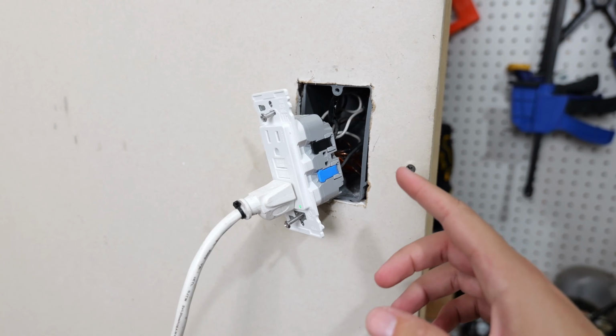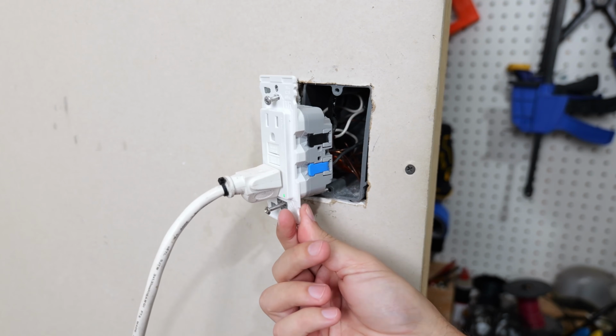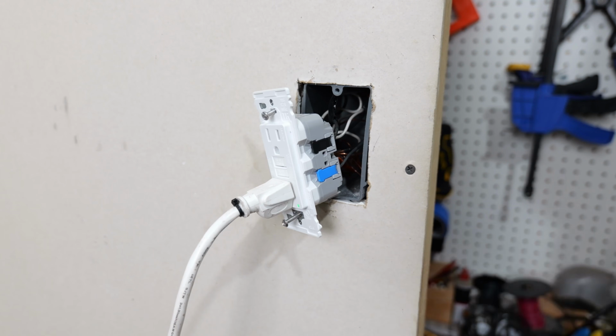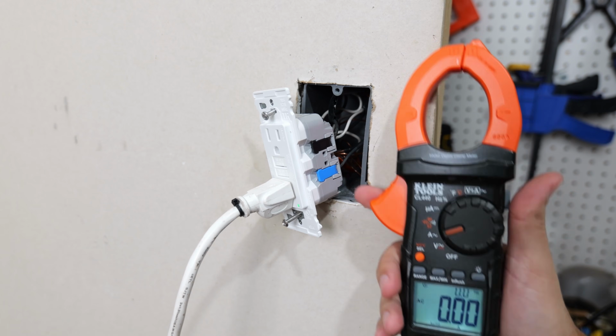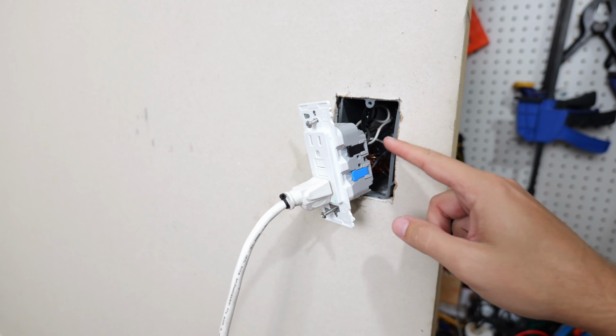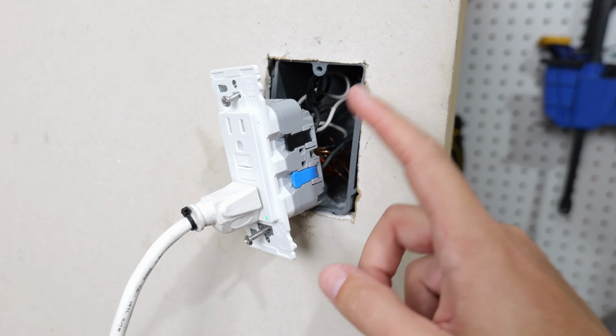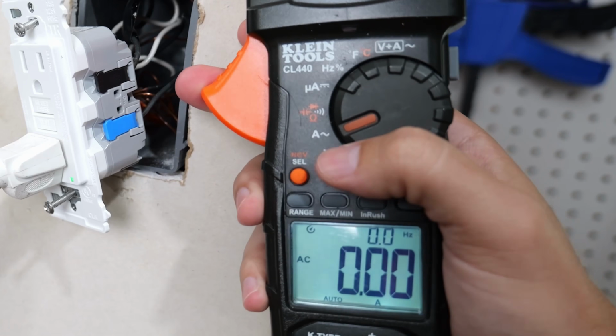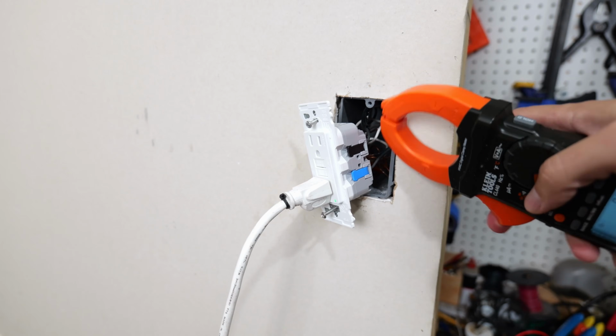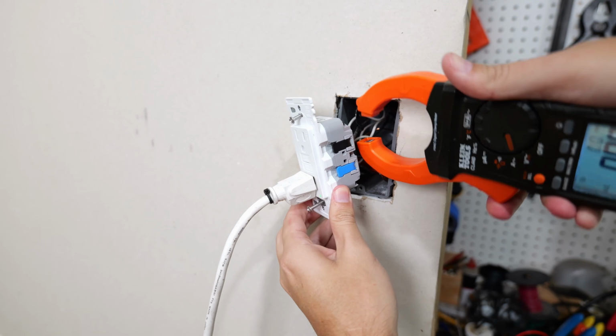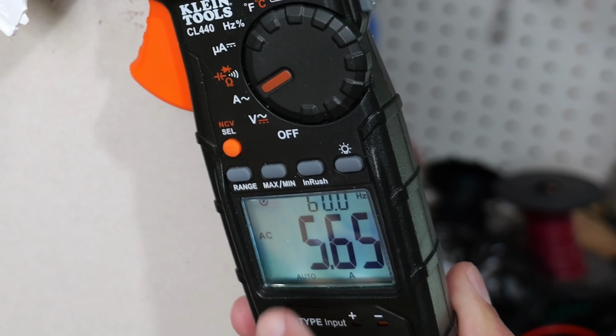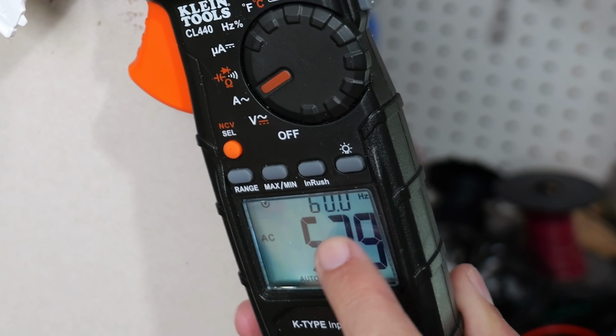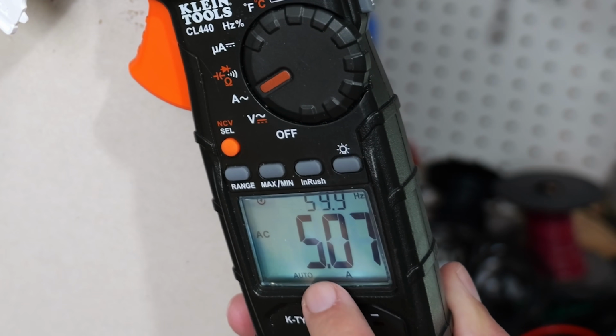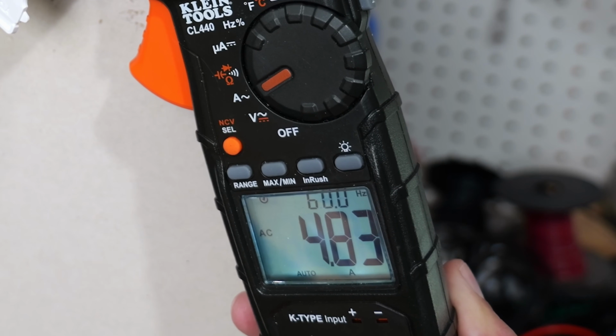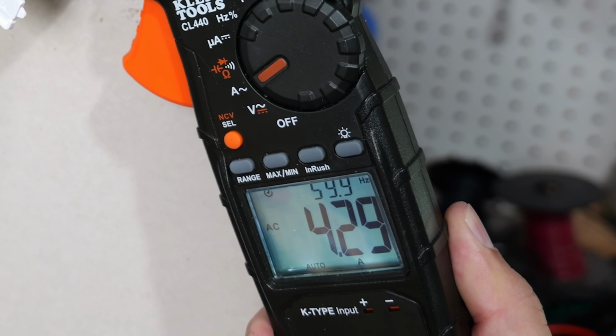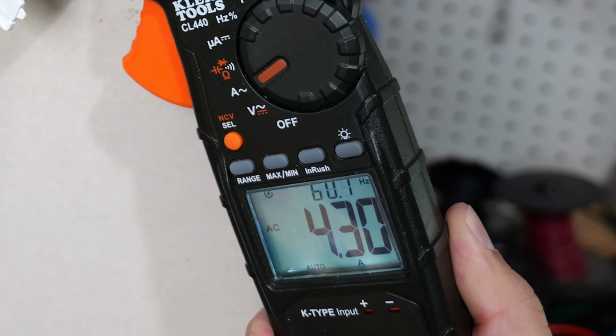Back over here at this receptacle, I've got it pulled out away from the wall. This is one way we can get our amperage reading on whatever we're trying to test using this clamp meter. We want to locate the hot wire in behind here that's supplying power to this receptacle. I've already got my meter set to that amperage reading I showed you a moment ago. All I need to do is get my clamp around my feed wire. As you can see, it's showing we've got 60 hertz, which is what we want to see, and we're currently getting around 5 amps of current draw for the AC unit. Now we're down to 4.2 amps, and I can hear the fan has decreased some, so that's why.